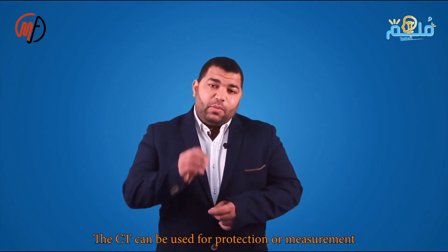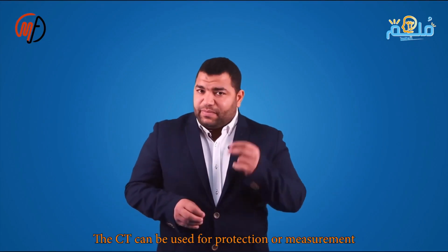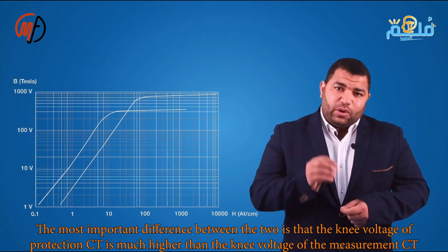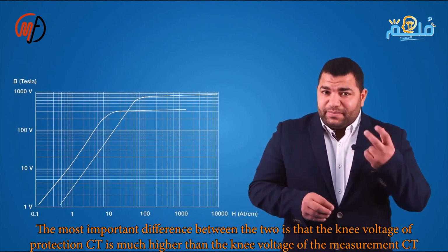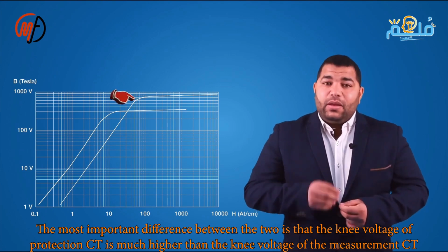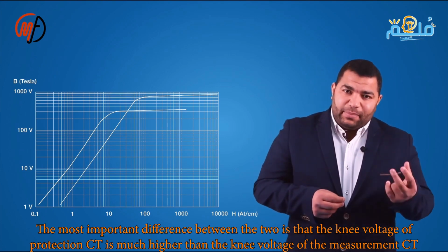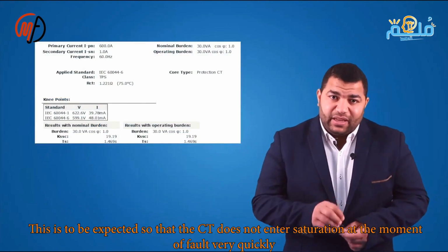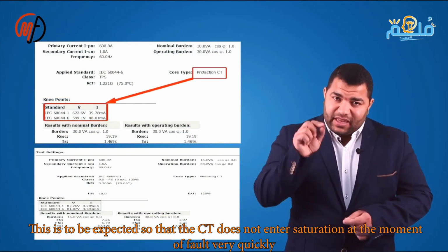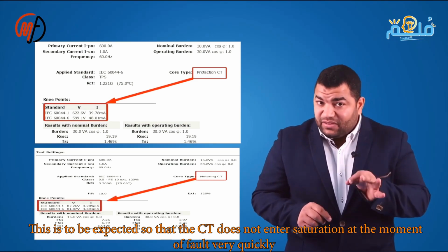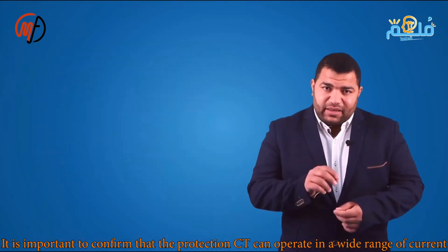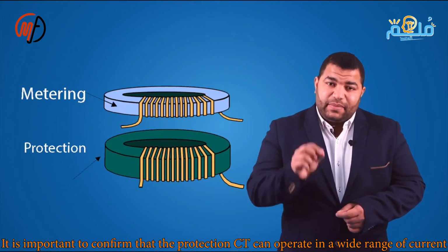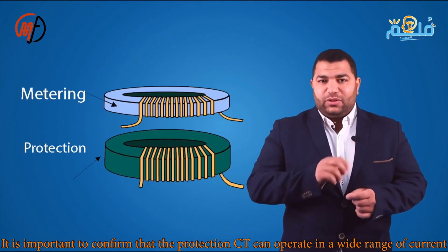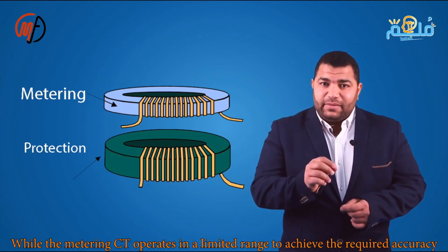The CT is used for protection or measurement. Protection CT has a higher knee point voltage than measuring CT. Protection CT operates over a wide current range, unlike metering CT, which is limited for accuracy. Protection CT has low accuracy, so during faults, 10,000 or 9,000 amperes make no difference. It has high saturation voltage and can transfer large currents to the relay.